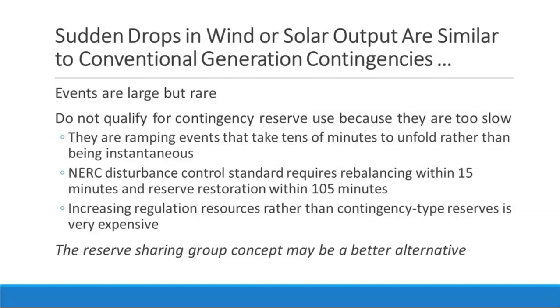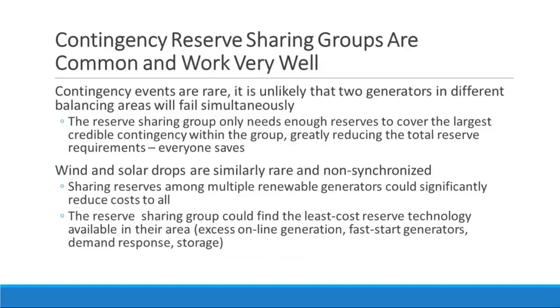Contingency reserve sharing groups are very common, well established, and work extremely well. Contingency events are very rare—it's unlikely that generators in different balancing areas will fail simultaneously. So a reserve sharing group of multiple balancing areas only needs enough reserves to cover the largest credible contingency within the group, greatly reducing the total reserve requirement, and everybody saves.